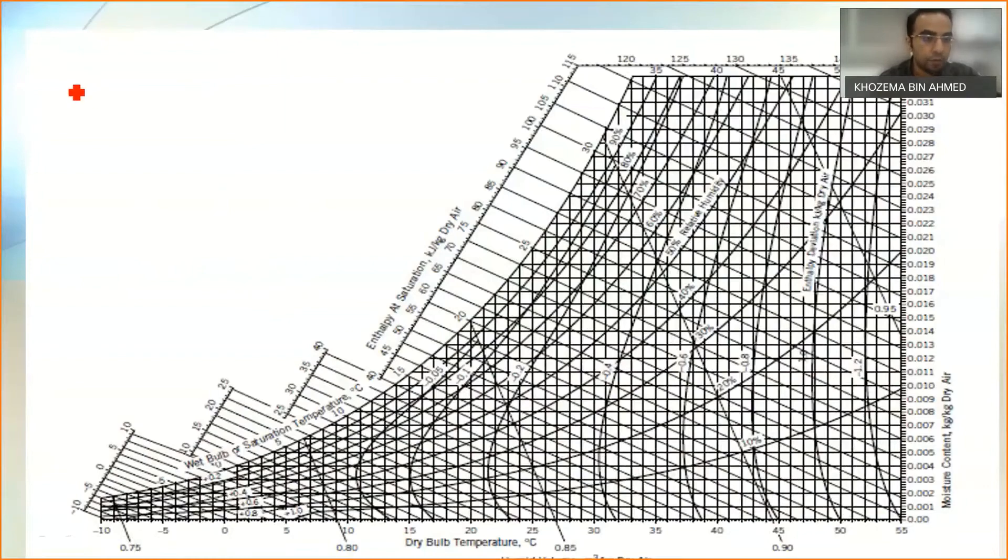From there I can find that my value of humidity at the point of intersection between 35 percent relative humidity and dry bulb temperature of 30 degrees Celsius, the humidity value is actually equal to 0.0093 kg H2O over kg dry air.